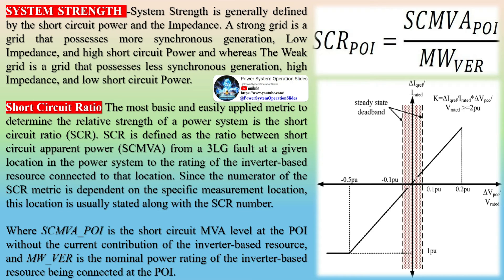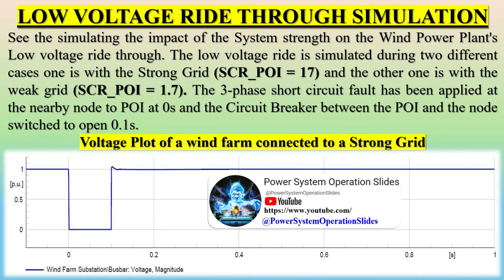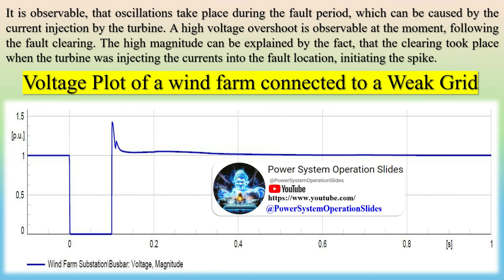Regarding Low Voltage Ride-Through: the grid operator requires that during a fault, the renewable plant must ride through the low-voltage occurrence at the system for the time frame mentioned in the grid code. In China, major blackouts have occurred as a result of entire wind parks tripping offline due to a brownout, increasing the focus on the LVRT feature of wind turbine control systems. The LVRT feature for renewable plants is much required to avoid cascading failures. It is observable that oscillations take place during the fault period, caused by current injection by the turbine, and a high voltage overshoot occurs following fault clearing — explained by the fact that clearing took place while the turbine was injecting currents into the fault location.